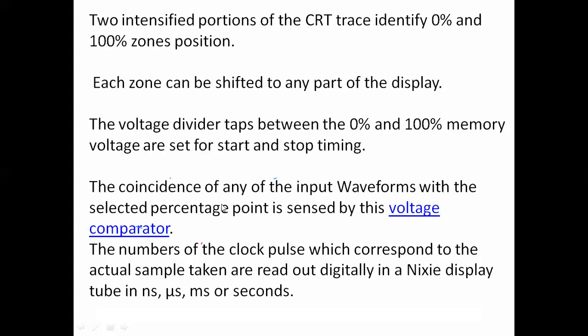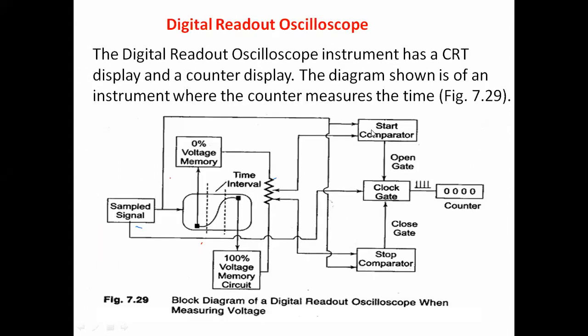The coincidence of any of the input waveforms with the selected percentage point is sensed by the voltage comparator. This comparator compares the sample signal with the selected voltage memory tapping — 0% tapping and 100% tapping. When the sample signal is compared with 0%, it produces the start pulse. When the sample signal is compared with 100% voltage memory, it produces the close pulse. In between, the clock gate produces samples that are counted for display.